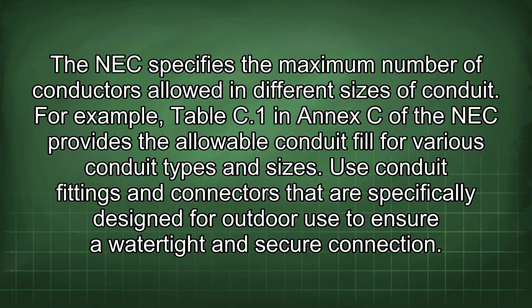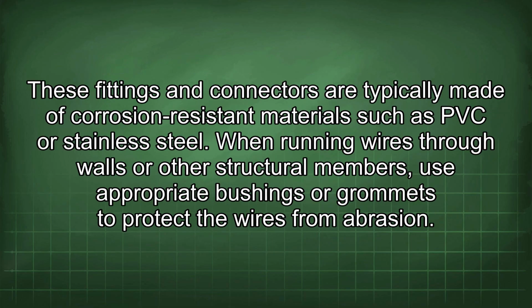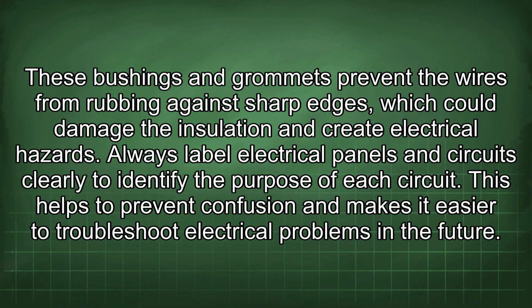For example, Table C.1 in Annex C of the NEC provides the allowable conduit fill for various conduit types and sizes. Use conduit fittings and connectors that are specifically designed for outdoor use to ensure watertight and secure connections. These fittings and connectors are typically made of corrosion-resistant materials such as PVC or stainless steel. When running wires through walls or other structural members, use appropriate bushings or grommets to protect the wires from abrasion. These bushings and grommets prevent the wires from rubbing against sharp edges, which could damage the insulation and create electrical hazards.